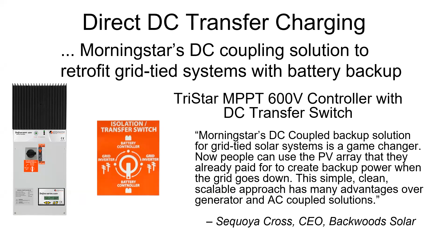To finish up on the direct transfer switch charging solution, you're looking at a lot less complexity. The switch is rated to 30 amps, so your max ISC according to NEC requirements can be 24 amps. It's intended to support two input strings, which can be combined on an internal bus bar underneath the enclosure faceplate. Everything is tidy, with tons of wiring room and a nice layout, just how an installer would want it. You have the pass-through connection to the grid-tied inverter terminals right there under the faceplate as well, all in one box for a tidy install.